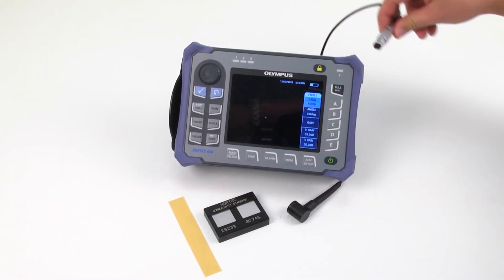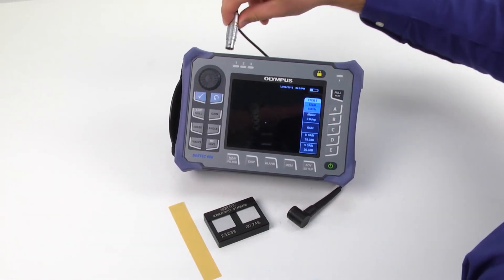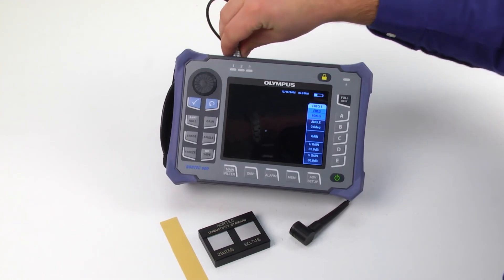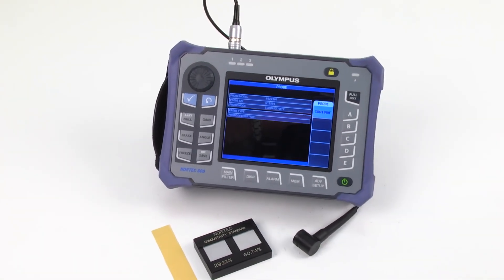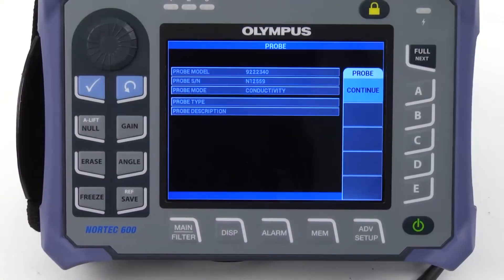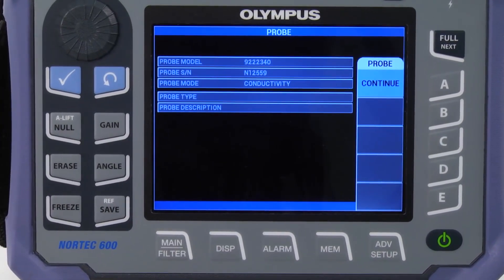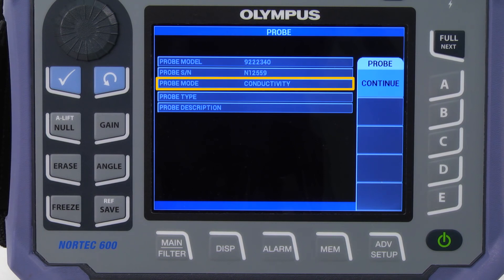When you connect the probe to the Nortec 600, a menu appears which gives information about the probe. It is important to note that the probe mode is automatically set to conductivity.